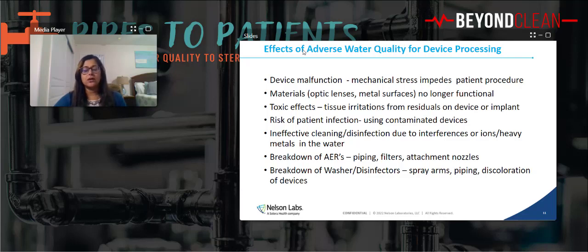Now, effects of water on device processing, right? What are we looking at? Device malfunction, mechanism stress, so it's not working properly, toxic effects, risk of patient infection, ineffective cleaning because we are not using the right water to prepare detergents, breakdown of AERs, right? Piping, filters, attachment nozzles. Are we even looking at those? Breakdown of washer disinfector, spray arms, pipings, discoloration of devices, right?